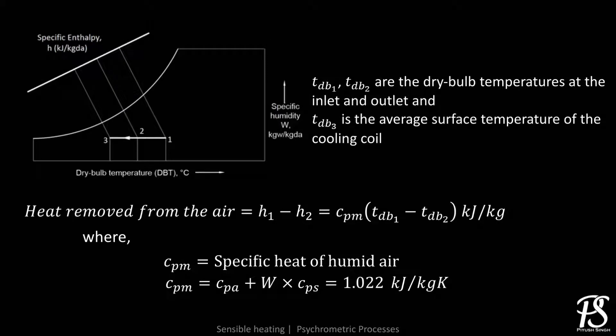The heat removed by the coil is equal to the difference between the inlet and the outlet enthalpy of air. Here, CPM is the specific heat of humid air, calculated using a given expression, where cpa is the specific heat of dry air and W is the specific humidity. Though the value of specific heat of humid air varies with the specific humidity of air, in most cases it is considered to be equal to 1.022 kJ per kg Kelvin.